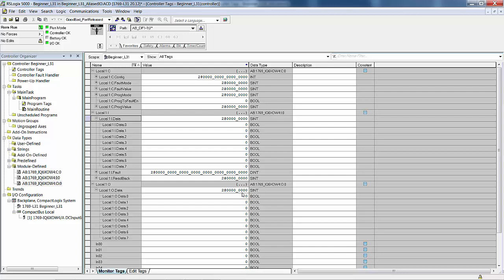And we specifically stated when an input circuit senses current flow greater than 1.5 milliamps, because remember, the solid state input circuitry has an off state and an on state. The off state is not necessarily zero, but it is anything below a certain threshold. In this case, 1.5 milliamps. So that's basically 1500 microamps, 1.5 thousandths of an amp.